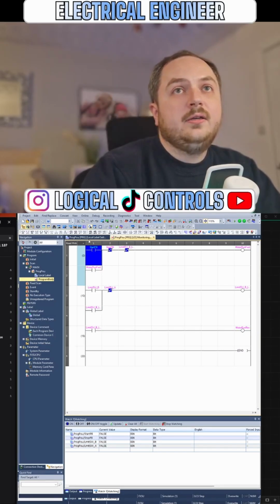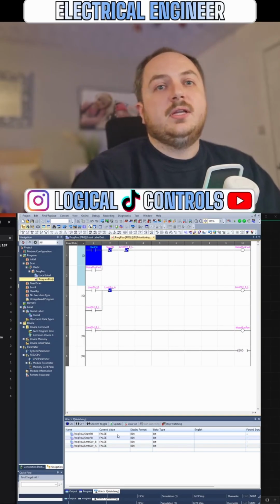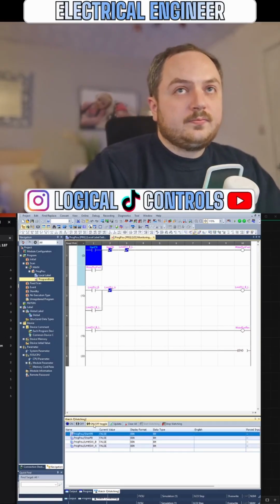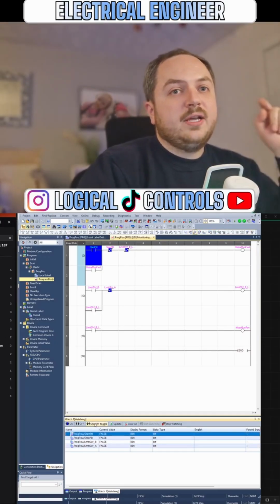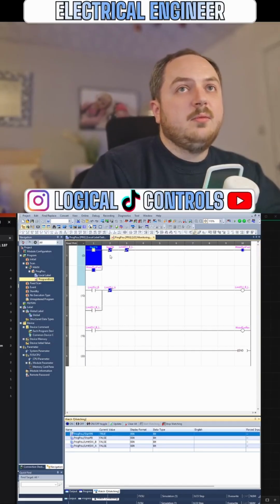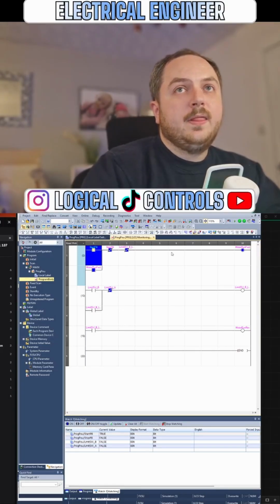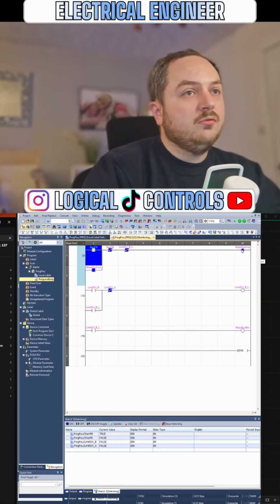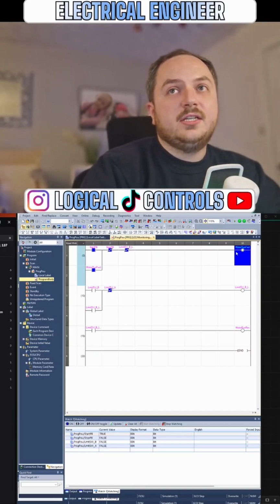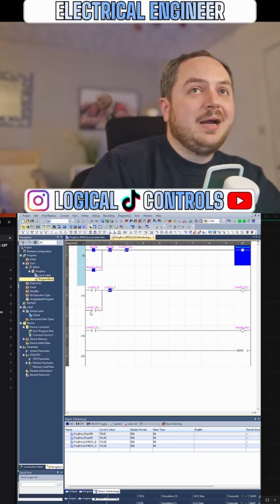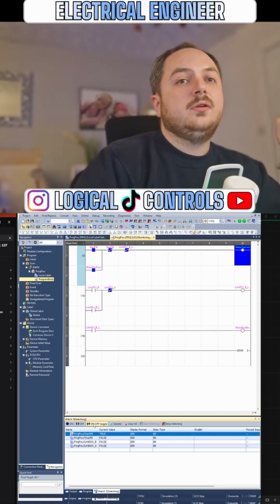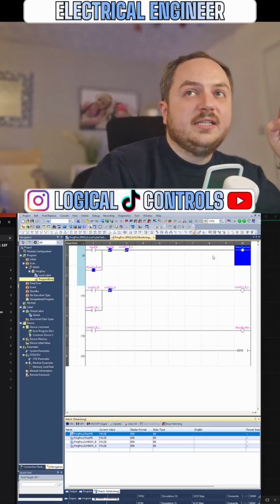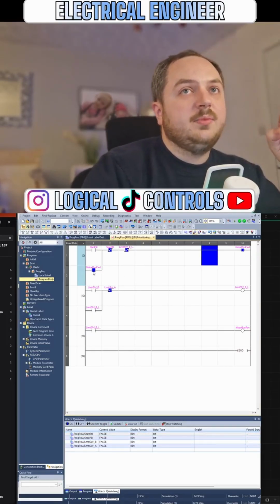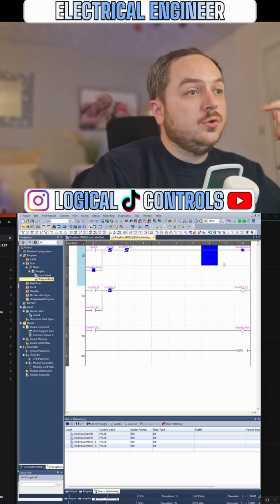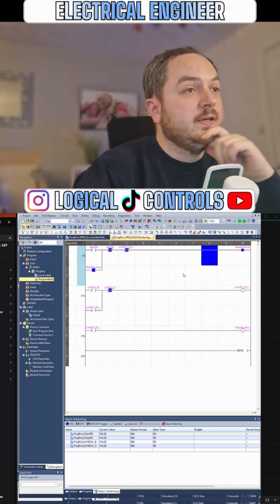We're still in simulation, so I can show you that. Step by step: I press the start button, it closes, you see it's gone blue - this has energized, motor run forward is energized now. I'm going to take my finger back off that start button, let me untoggle that - but you see it's still held on, still energized, and that's because there's a contact of itself keeping it energized. That's what's called a latching circuit or a holding circuit.